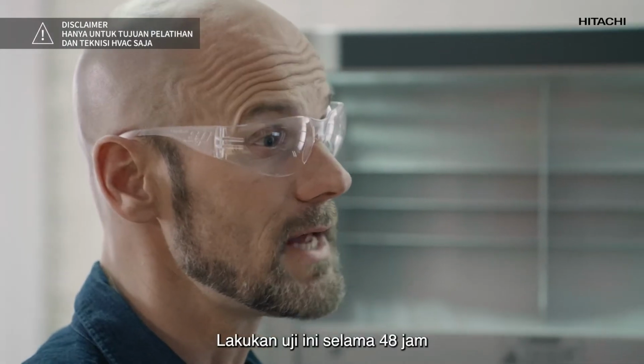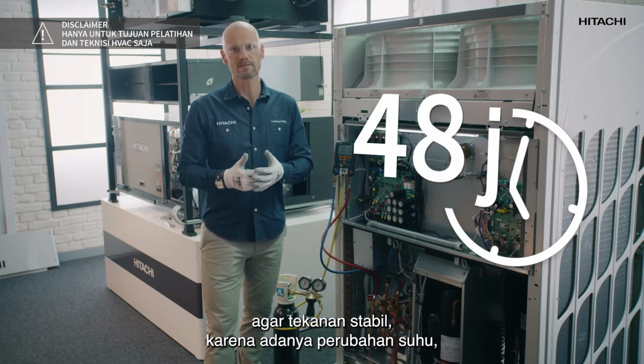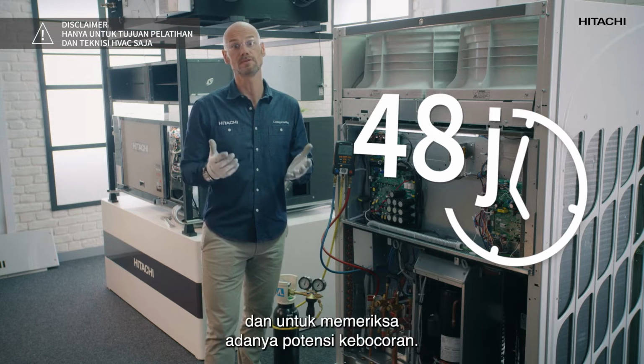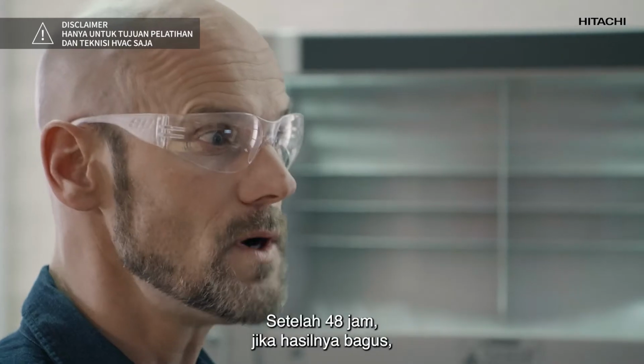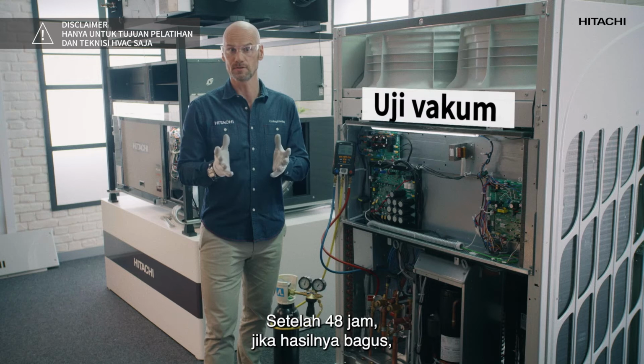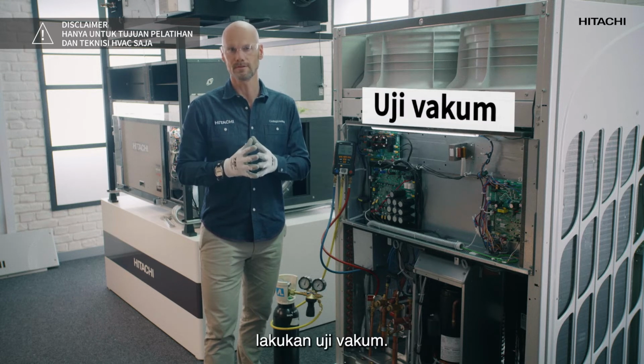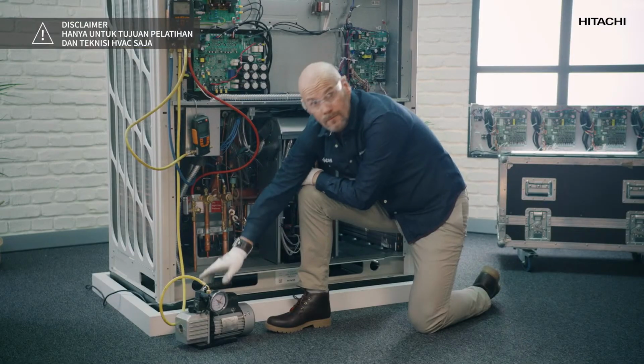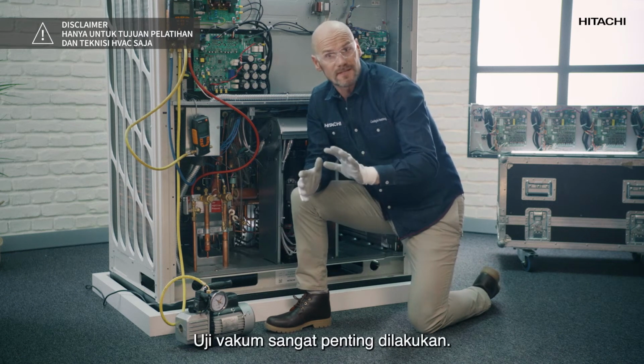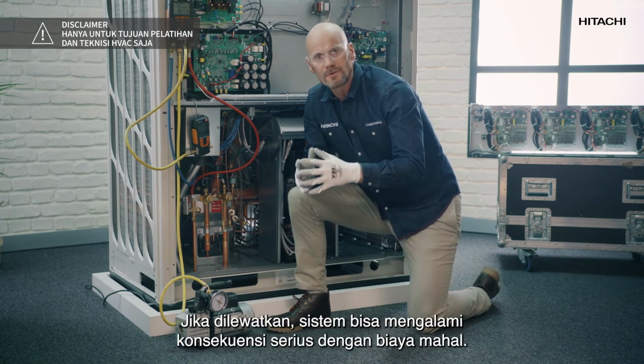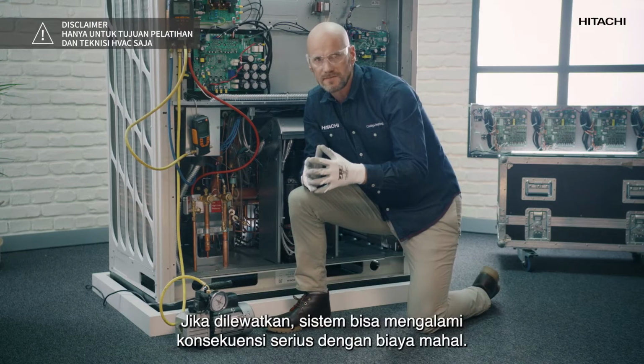The test must be carried out for 48 hours to stabilize the pressures due to temperature changes and to check for any possible leaks. Once the 48 hours have passed and the results are okay, we now perform the vacuum test. The vacuum test is very important. Not doing it could have serious and costly consequences for the system.